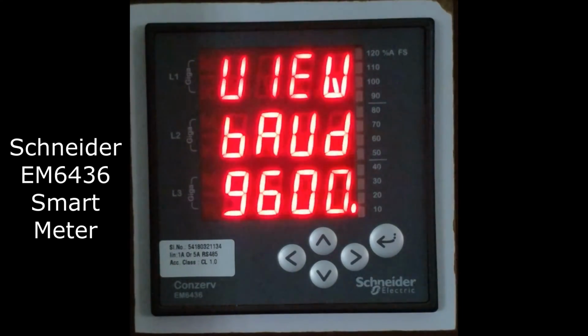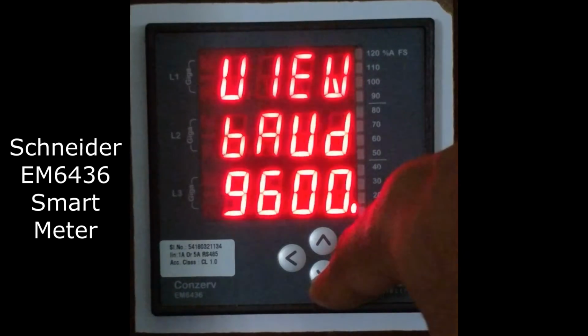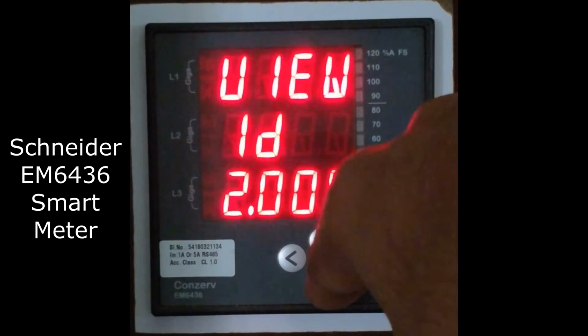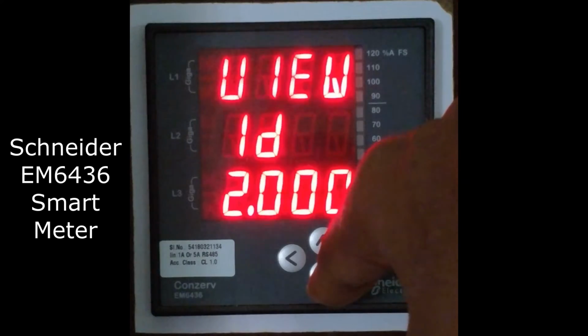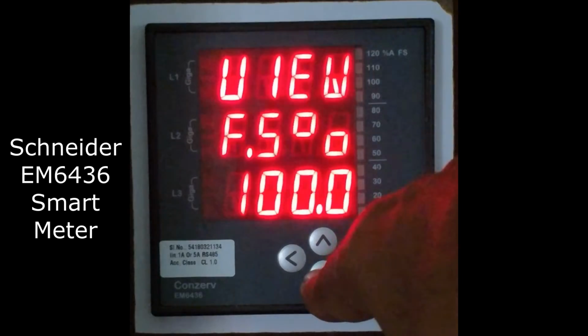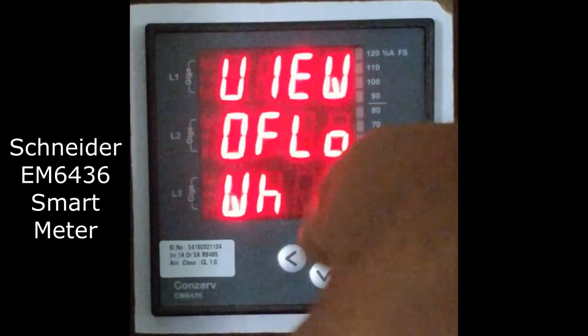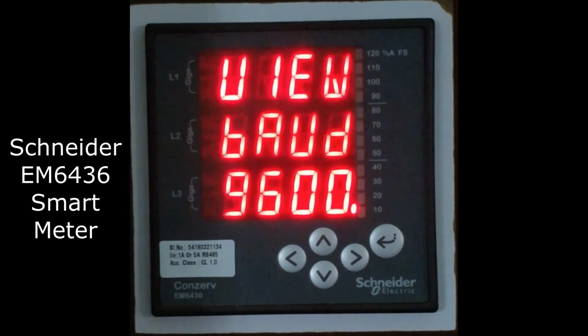You can see the baud rate is currently set at 9600. Parity is even. ID, basically the slave ID for the Modbus, is 2. And these are the other things. The important parameters that we want are the baud rate, the ID, and the parity. The meter in the picture has an ID of 2, but for the demonstration I'll be reading with a meter that has an ID of 1.